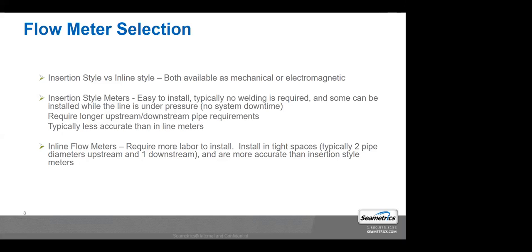Inline meters are going to require more labor to install. The advantages are you can put them in extremely tight spaces. They are calibrated to a known accuracy at the manufacturer's lab. They're typically NIST traceable with that calibration report, so they're going to be just more accurate.